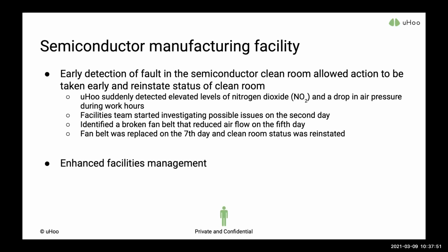They were able to resolve this issue within just a few days, because with the proper data you can identify issues, get your facilities team involved, and immediately address them. They were able to reinstate the clean room status. Without this kind of data, they wouldn't have been able to identify the problem, and would just have had a polluted clean room continuously.